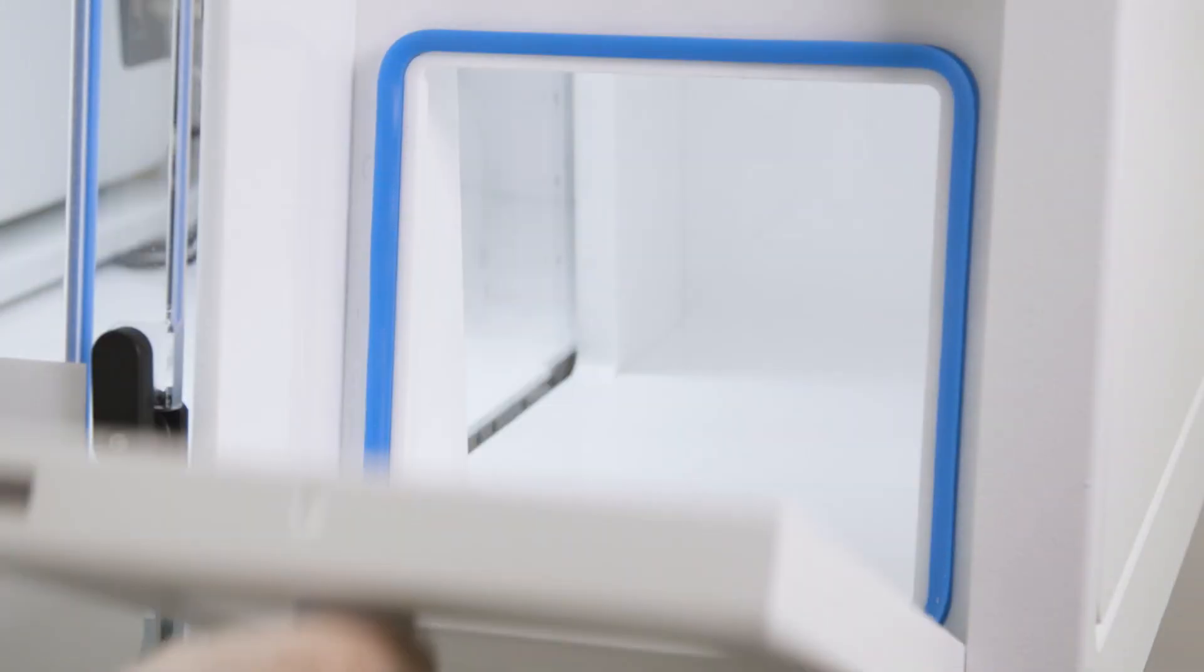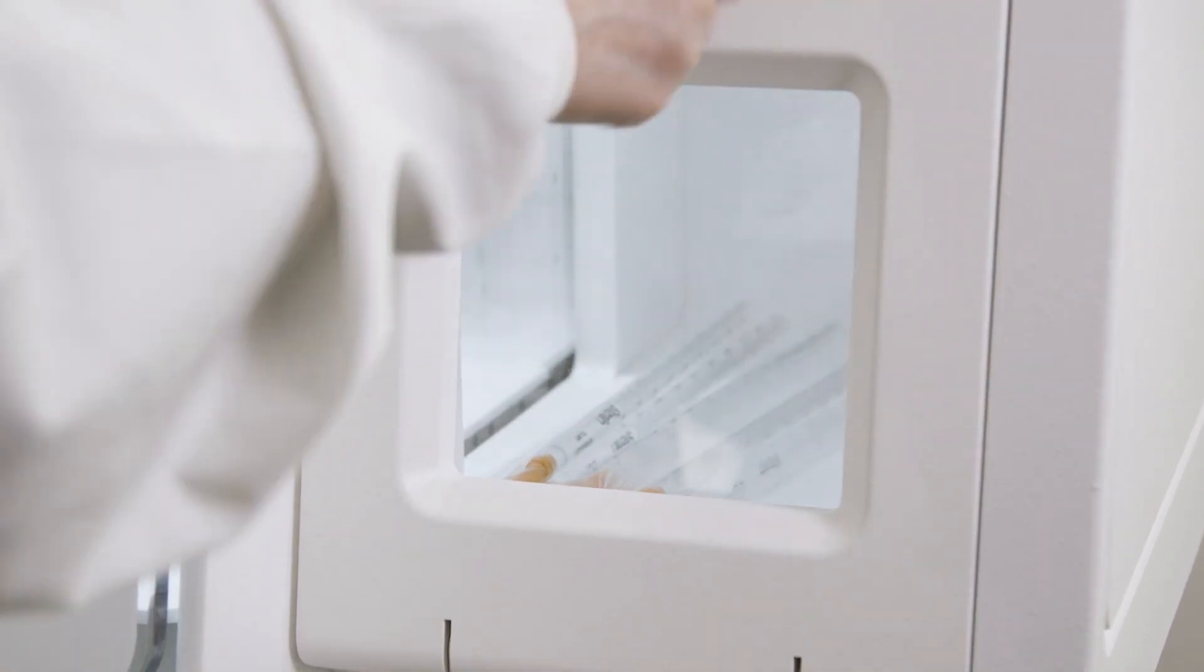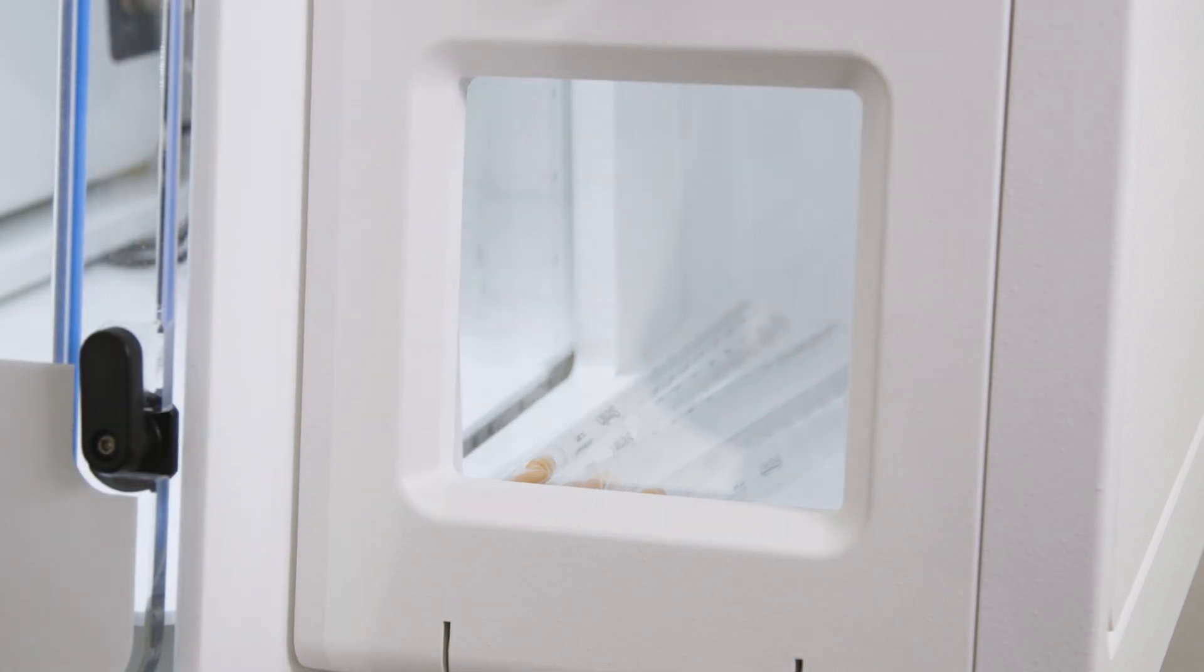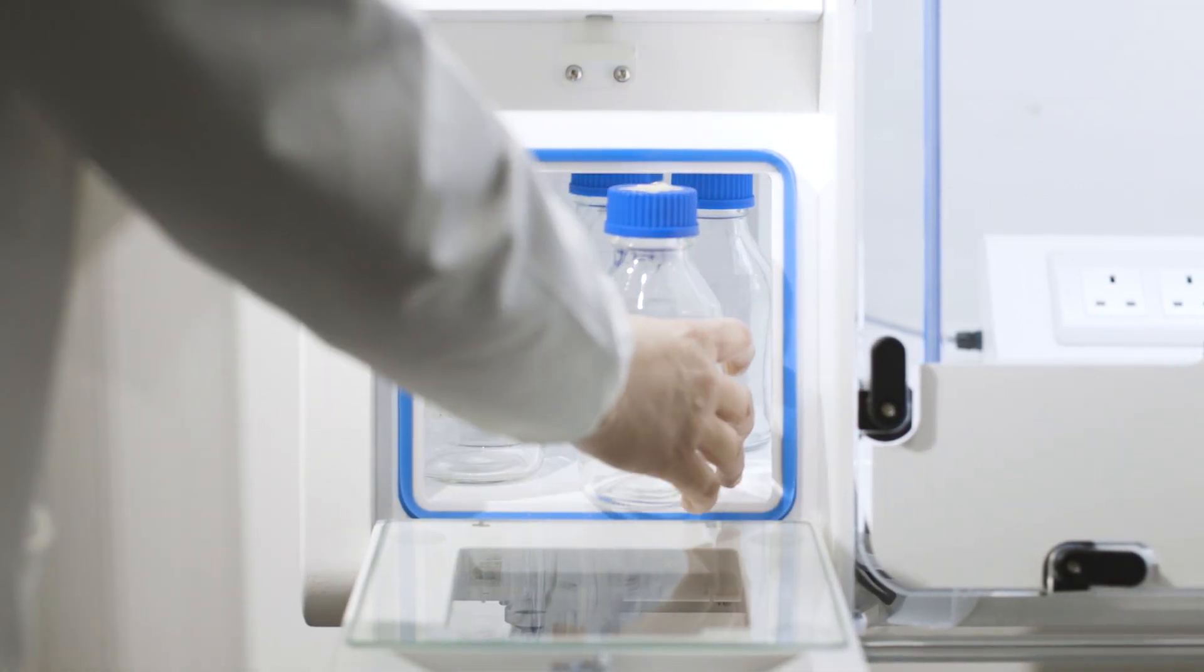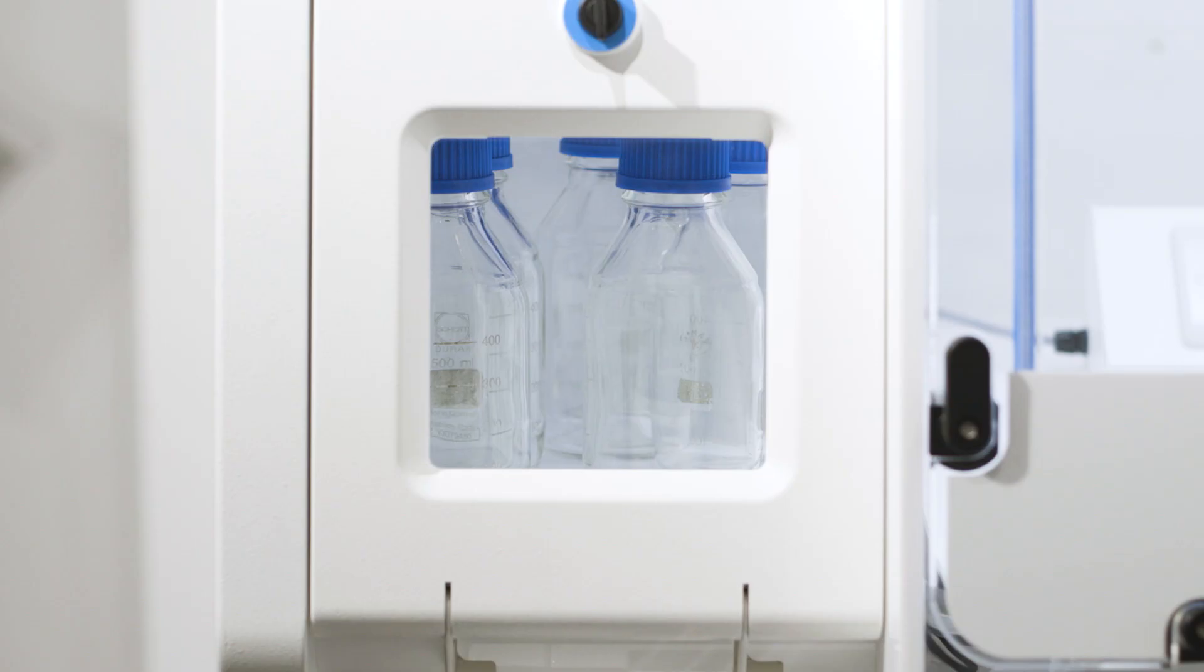The Whitley A155 HEPA workstation includes two rapid airlocks, one at either end of the chamber, each able to accommodate ten 500 milliliter duran bottles. Even though these airlocks are deeper than those in our smaller workstations, the cycle time is still only 60 seconds.